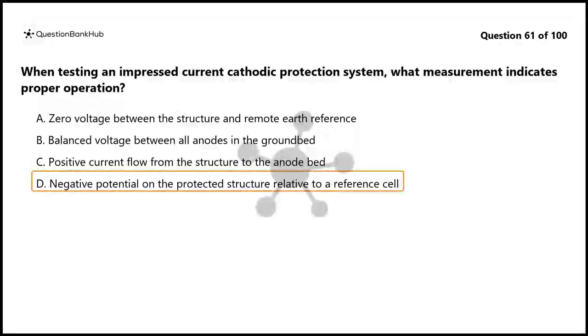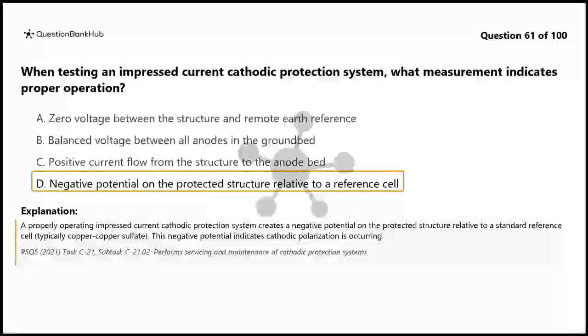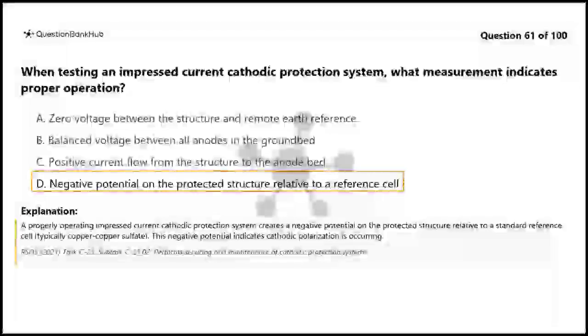The correct answer is D. Negative potential on the protected structure relative to a reference cell. A properly operating impressed current cathodic protection system creates a negative potential on the protected structure relative to a standard reference cell, typically copper sulfate. This negative potential indicates cathodic polarization is occurring.